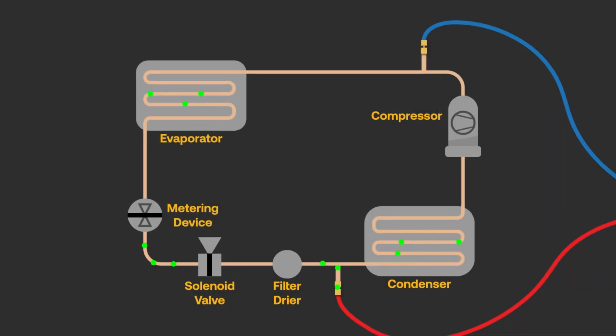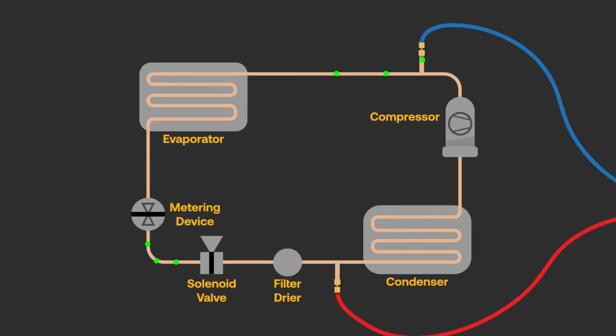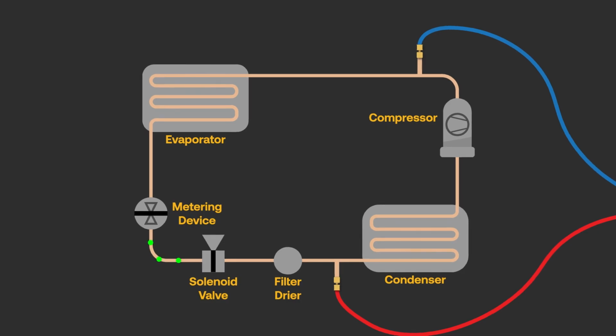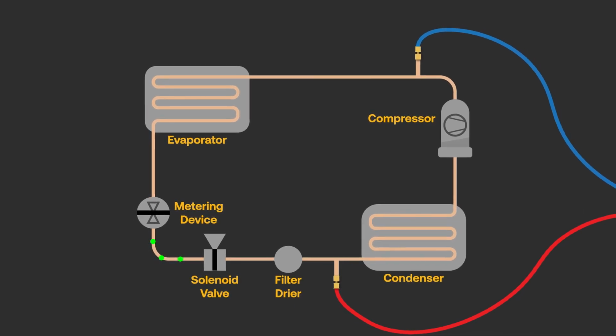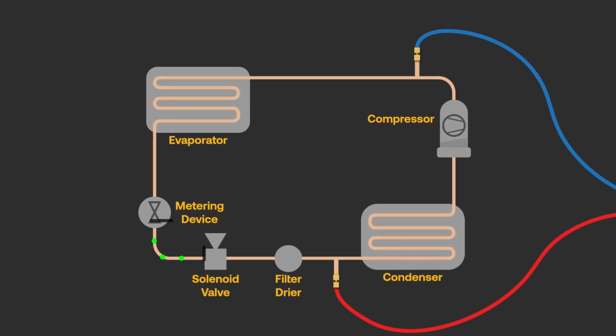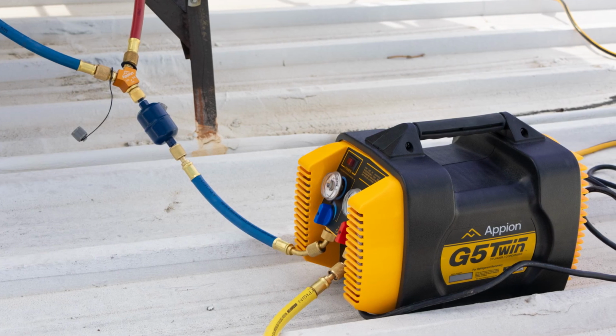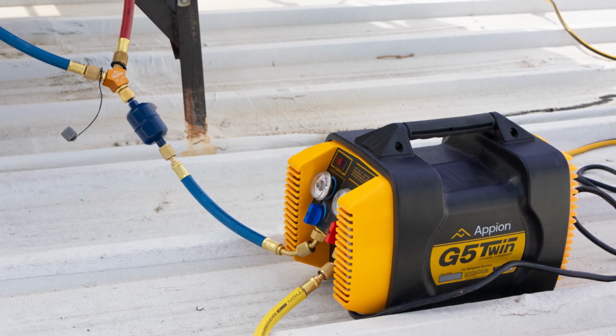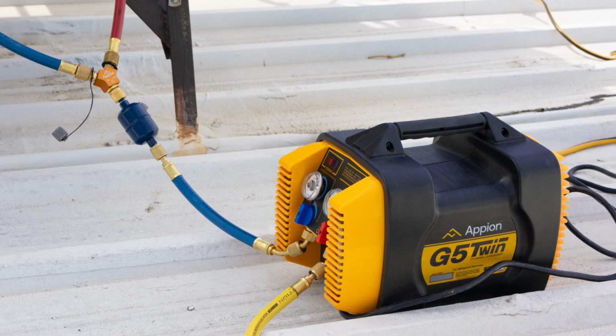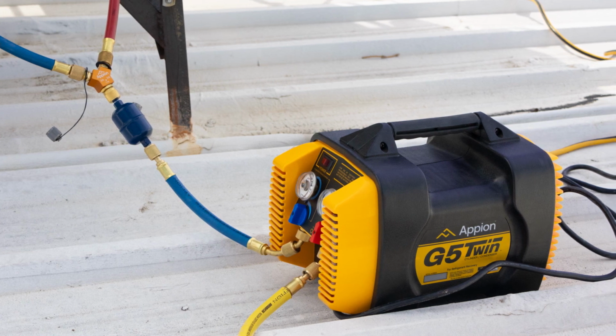Also, it's important to ensure refrigerant cannot be trapped by solenoid valves, expansion valves, and branch boxes. These components can be controlled by magnets or onboard system controls to ensure full flow and full refrigerant recovery. Now that you have an understanding of proper equipment performance and basic full flow principles, we can review advanced full flow practices deployed during the recovery process.